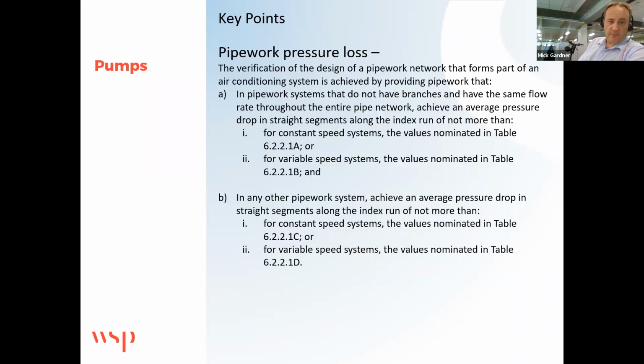Also, we're looking at pipework pressure losses. They're looking also at pump motors, because pumps and fans are always constantly running. So we've got to verify the design of the pipework. In a pipework system that does not have branches and has the same flow rate through the entire pipework network, achieve an average pressure drop in straight lengths along the index run of not more than, and then there's a series of tables, which are on the next slide.